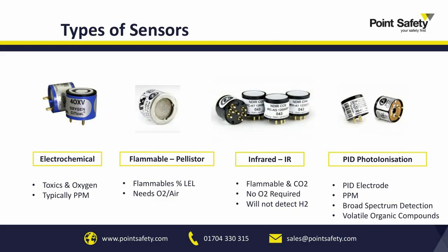Now, portable detectors will have gas detection sensors within them of different technologies. Firstly, you'll have electrochemical sensors. These will be typically for your toxic gases and your oxygen sensors. They'll read in ppm, or percent volume if it's oxygen. They're your very stable sensors, normally with a life between 2 to 5 years, depending on the gas. Some of the toxics do only have 1 year life, so that's important to recognize when you're looking at service contracts and ongoing servicing requirements.